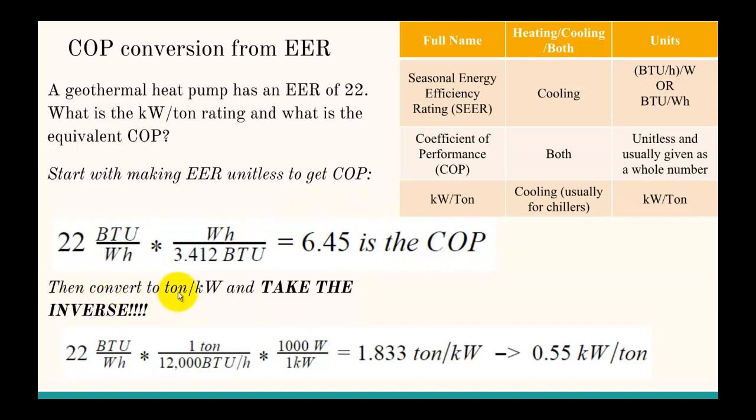Then we need to convert to tons per kilowatt, and then take the inverse. Because remember, the weird part about kilowatts per ton is that it's not output over input, it's input over output. So we have the 22 BTUs per watt hour, and then we take the ton unit conversion, which is 12,000 BTUs per hour, then we take the watts to kilowatts, and we get 1.833 tons per kilowatt.